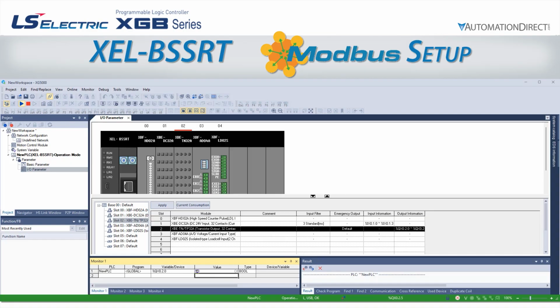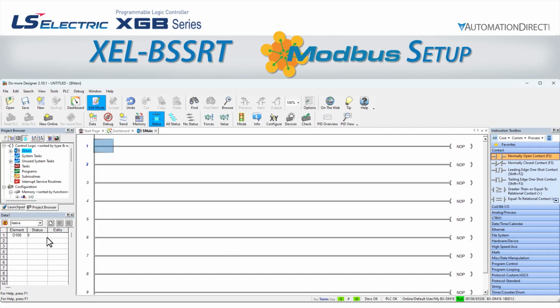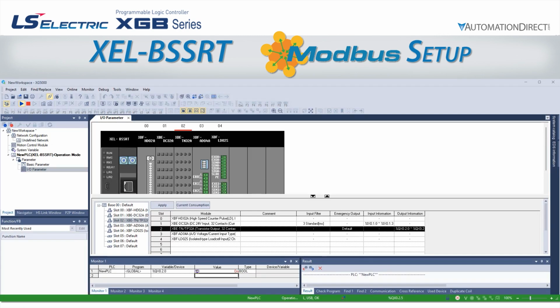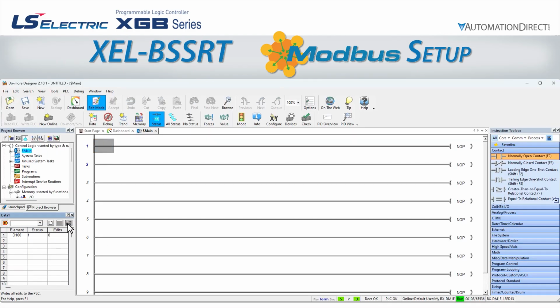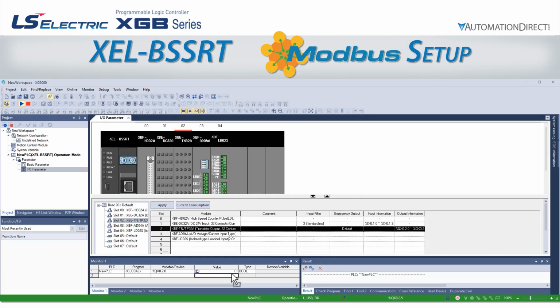We go back to Do More Designer, and we write a 1 into the edit column for the D100. If we now send this edit to the PLC, and go back over to XG5000, we can see that the BSSRT has been commanded to turn on the first output point of the TN32A card in slot 2. Back to Do More Designer, we'll write a 0 to D100, and back to XG5000, and the output point is back off. Perfect.